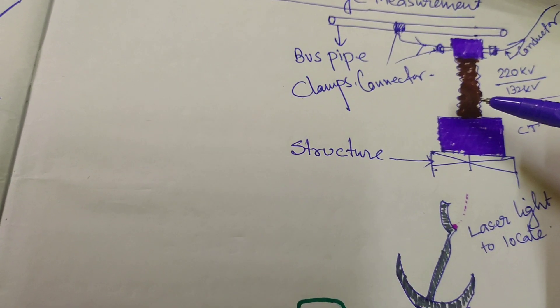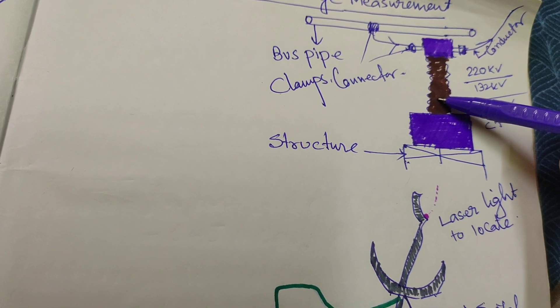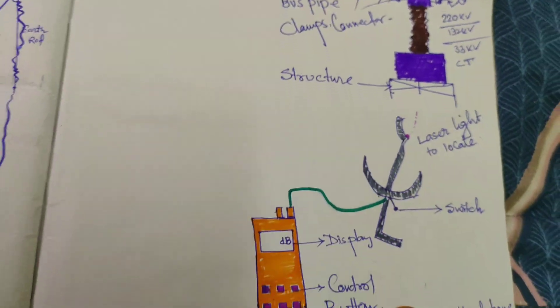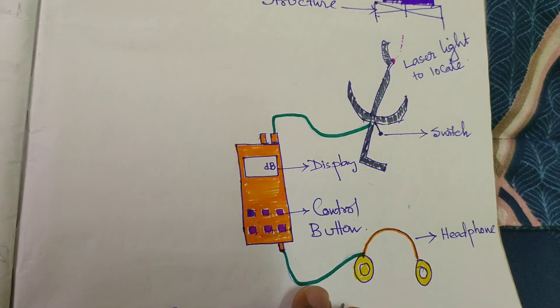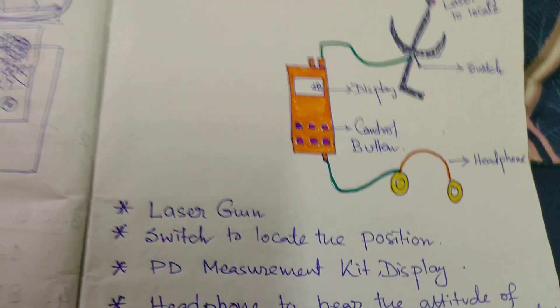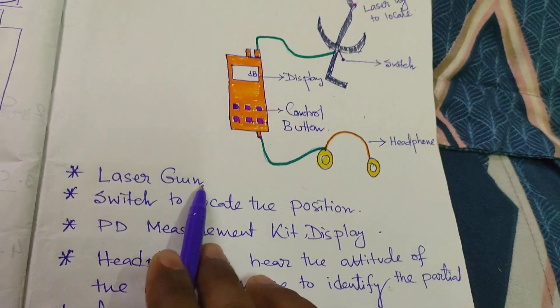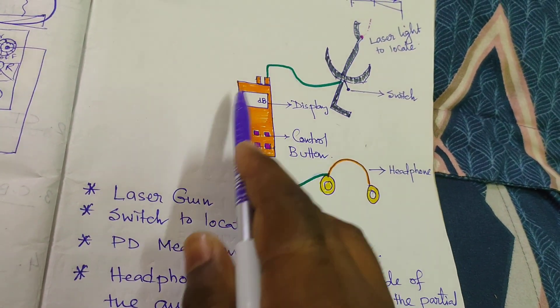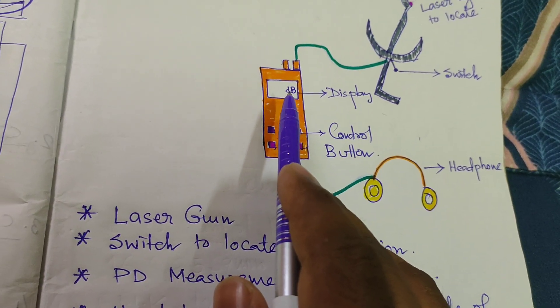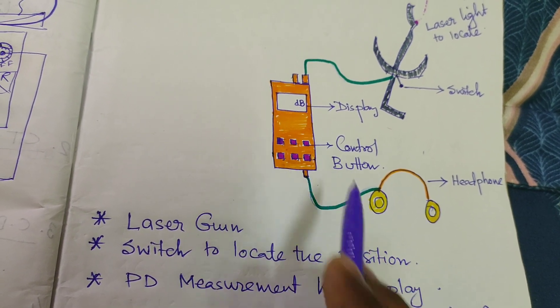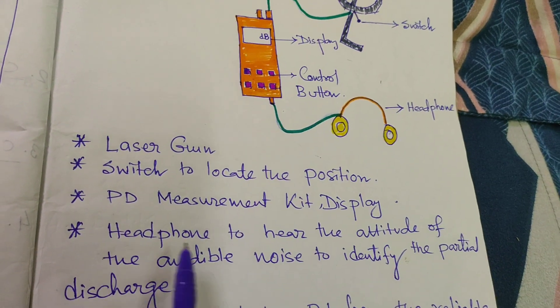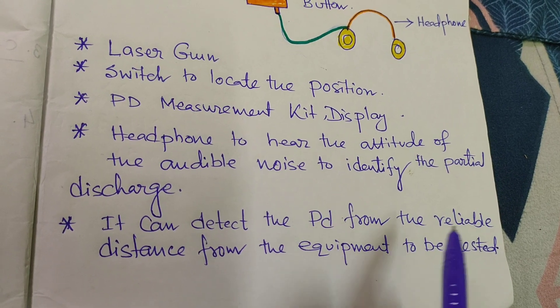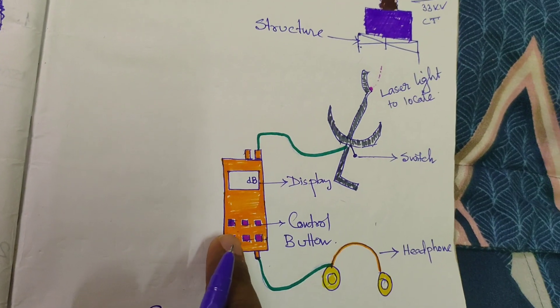That will decrease your revenues, damage your properties, and may harm your working personnel across the switchyard. So you have to identify it by help of this PD machine. The partial discharge kit consists of: a laser gun switch to locate the position, the PD measurement kit and display showing how many decibels of noise you are finding, and headphones to hear the audible noise to identify partial discharge. It can detect PD from a reliable distance from the equipment to be tested.